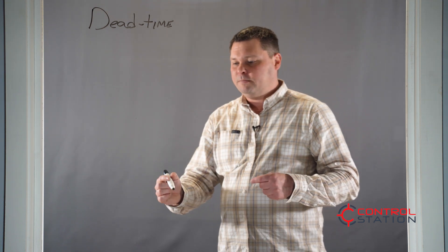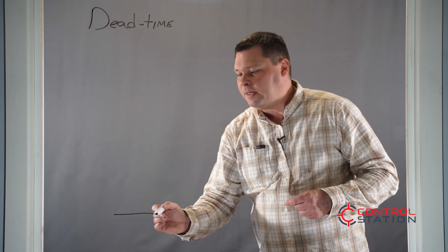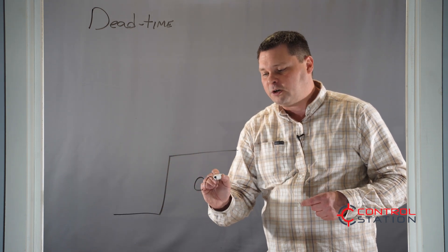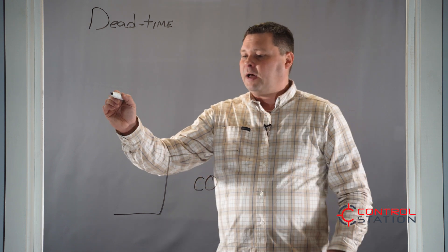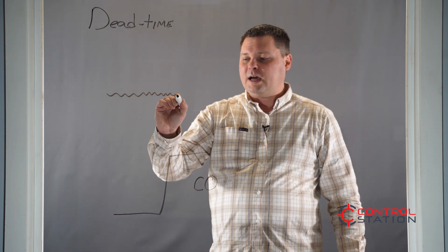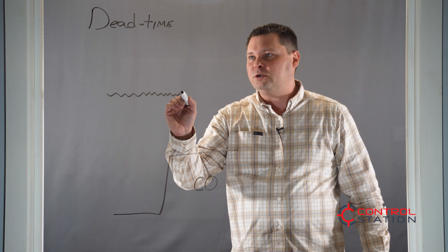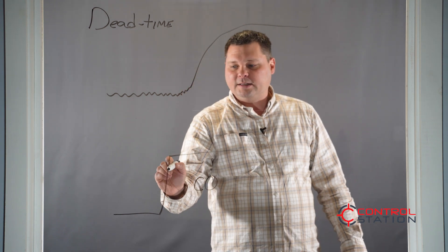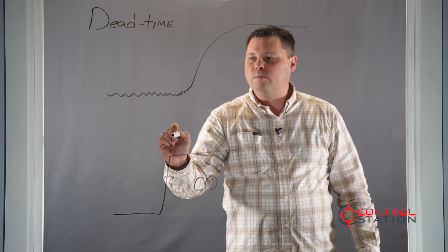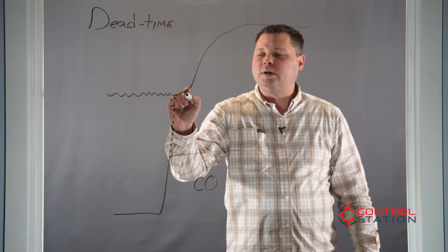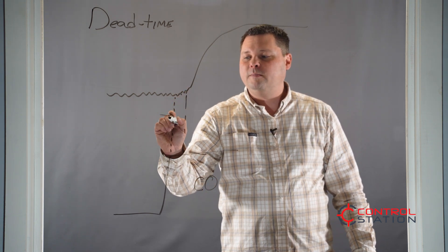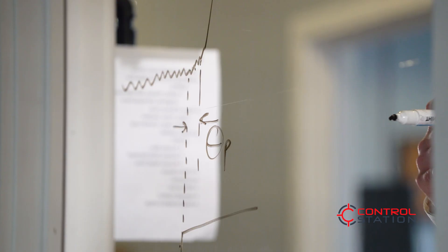So what is dead time? Dead time is the time it takes from when you make a change to the output. So if this is our controller output and we've got a process variable, it's the time it takes from when you make a change till something actually starts to occur in the process. It's the difference from the time you made the change till something actually started to happen. This difference is known as theta, or the dead time of a system. It is the delay.